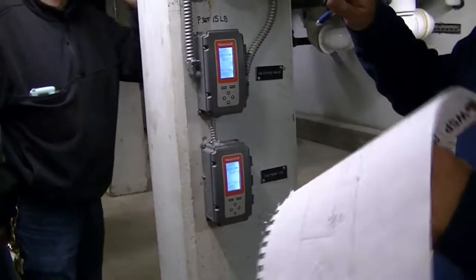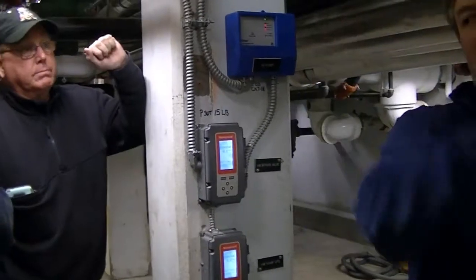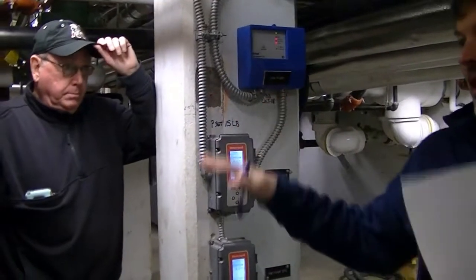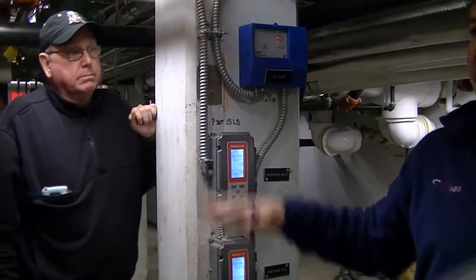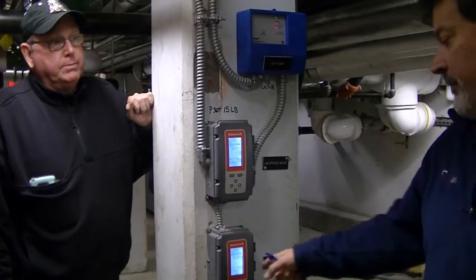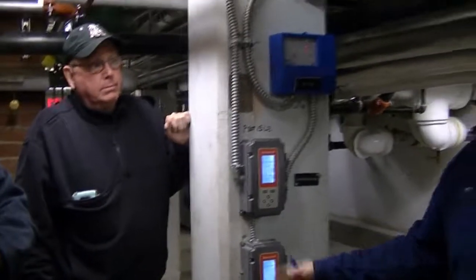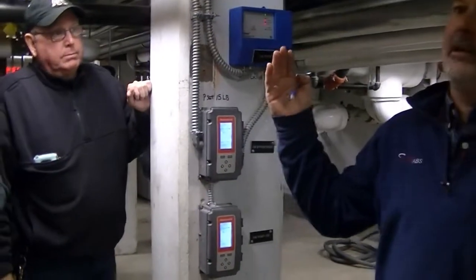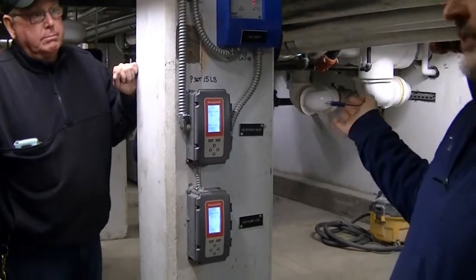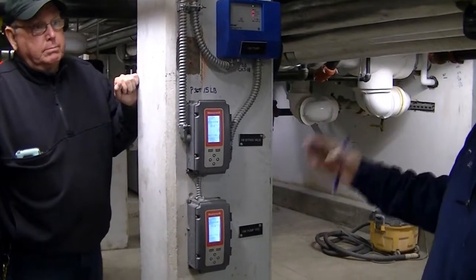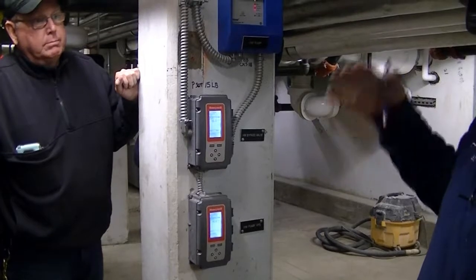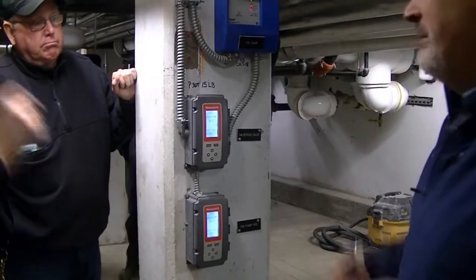I don't know if that's going to get changed once all these sides of these buildings are done and there's water balancing, where the balancer might pick a different set point. But for now, we have them at 15, okay? 15 did work the last winter, so it's okay. It's enough. You might be able to lower that set point for more energy savings, but there might be more complaints then.